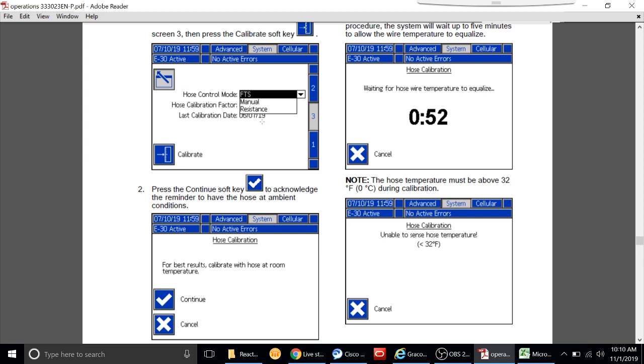Just tap it down twice. It goes in resistance mode, and then you'll hit enter, and that enables that resistance mode. Got it. Now I see this other little button here that pops up. It says calibrate. What is that for? So what that's for is we need to calibrate that hose to the system so we know how much length we have on the system, right? And that helps us determine temperature of that hose. Okay, that makes sense.